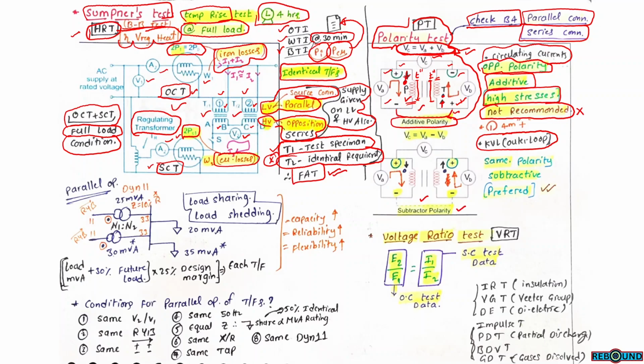For subtractive polarity, on the primary side, we have considered a dot here and this is the current direction. On the secondary side, we have considered a dot here. This is the current direction. So in this case, by the time current enters the primary, at the same time, the current is leaving the secondary. So there are no circulating currents in this case. So this is the same polarity on primary side and secondary side.